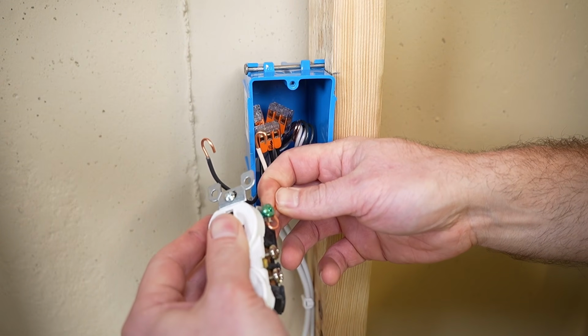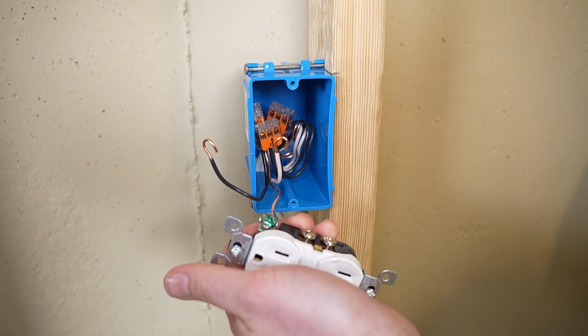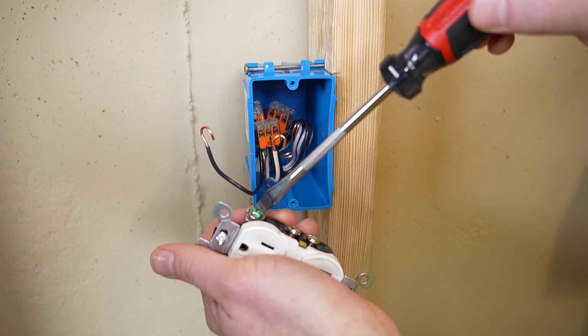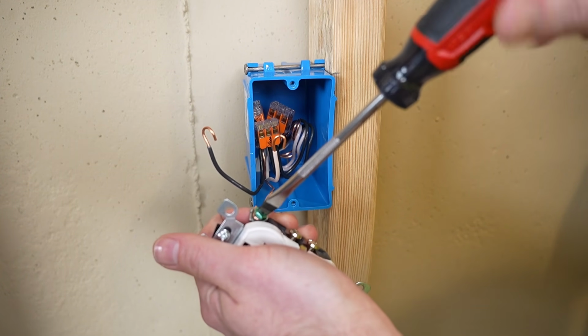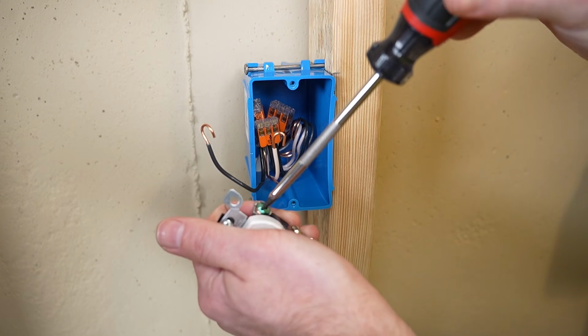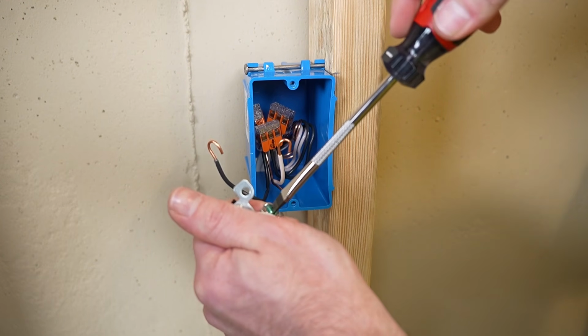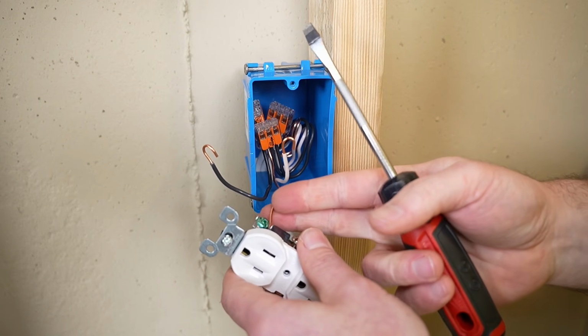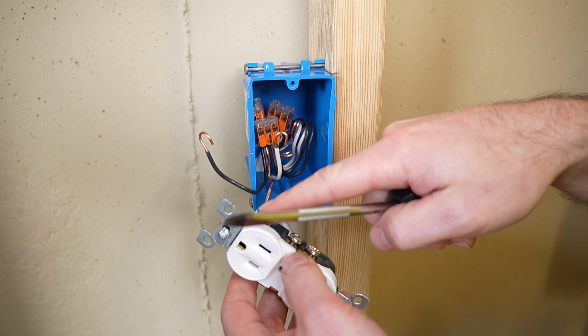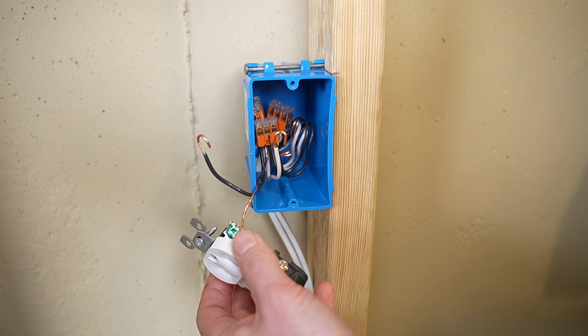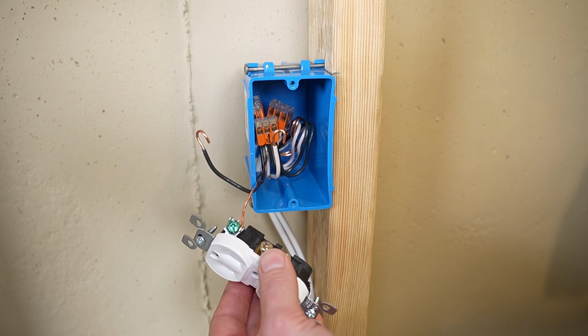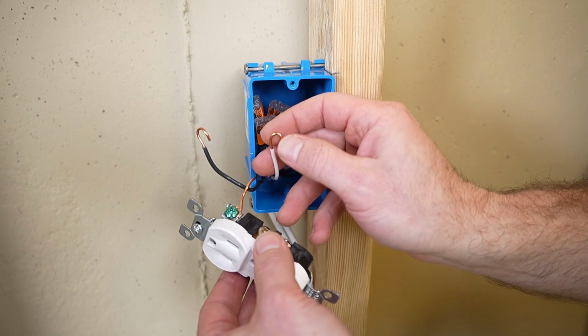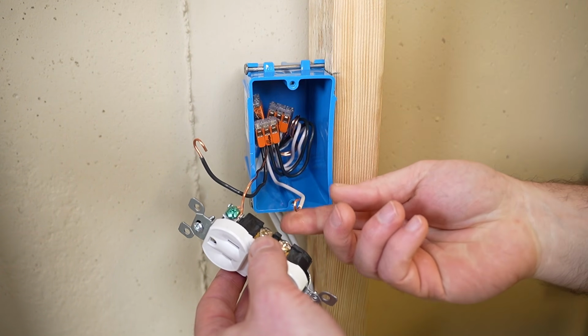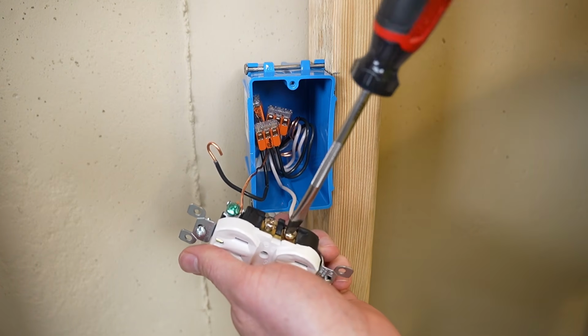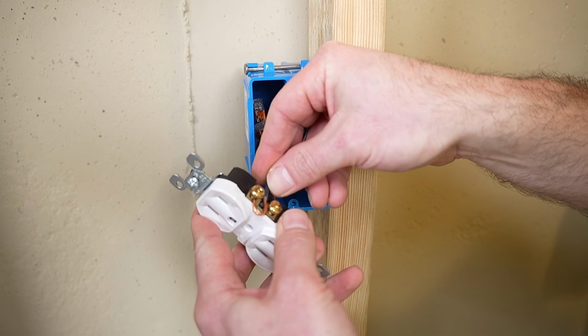It is good practice to land the ground first. That way, if something becomes energized while you are working on it, remember, you should never work on live circuits. Always shut your circuits off. But in the event something goes wrong, having a solid ground there is a lot better of an opportunity to trip the overcurrent device, shutting the circuit off in the event of a short circuit. And our neutral, and finally the hot.